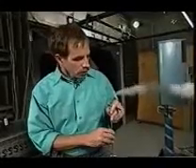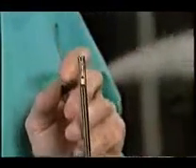Another method we can use to measure flow velocity is by looking at the effect that the airflow has on cooling or the thermal properties of a probe. So this is an example of what we call a hot wire probe. And basically the way it works is the air flowing by this thin element at a constant temperature by running current through it. And by knowing the calibration of the device, we can infer what the flow velocity is by how much current we need to put into the element to keep it at a constant temperature.